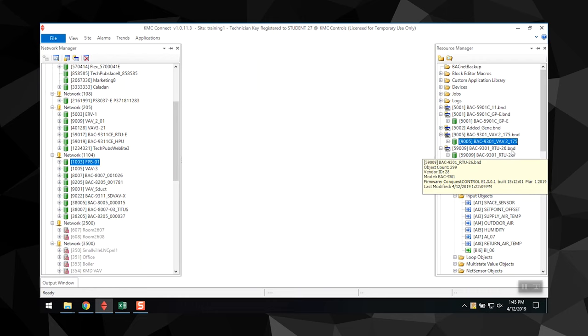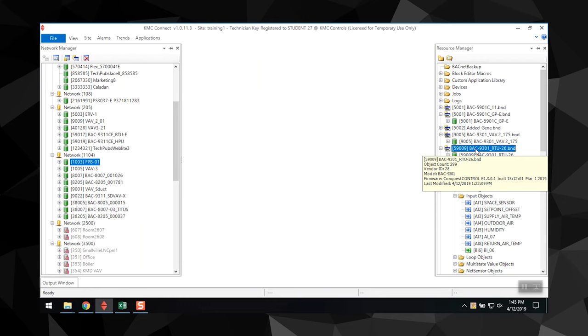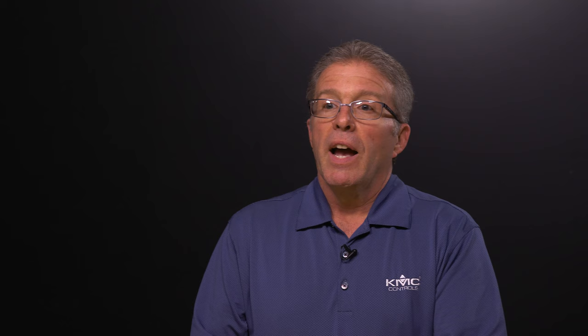You can also create backup files by dragging an item from the network manager to the resource manager. For BACnet devices and objects, a .bnd file is added to the resource manager list. For KMC controllers and points, a .kmd file is created.